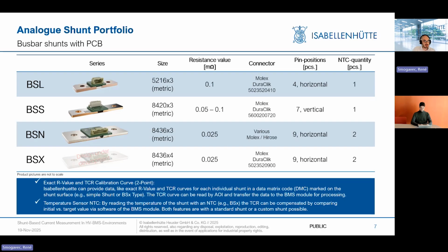that has a DMC code laser printed on the shunt body, which gives us the opportunity to calibrate the resistance value for every single individual shunt at the end of line and save it in the DMC, meaning we can achieve plus minus 0.1 to 0.2% initial tolerance, which is more reasonable for today's RFIs and RFQs.